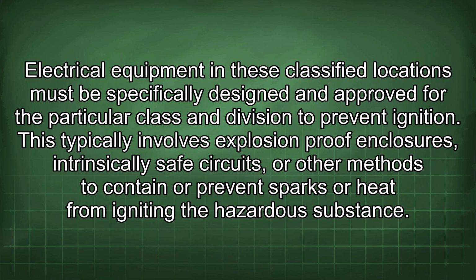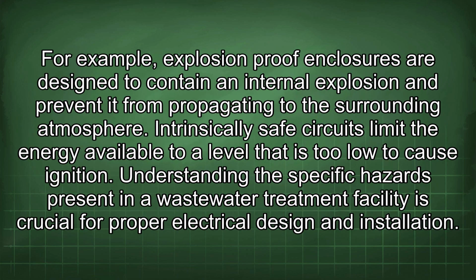Electrical equipment in these classified locations must be specifically designed and approved for the particular class and division to prevent ignition. This typically involves explosion-proof enclosures, intrinsically safe circuits, or other methods to contain or prevent sparks or heat from igniting the hazardous substance. For example, explosion-proof enclosures are designed to contain an internal explosion and prevent it from propagating to the surrounding atmosphere. Intrinsically safe circuits limit the energy available to a level that is too low to cause ignition. Understanding the specific hazards present in a wastewater treatment facility is crucial for proper electrical design and installation.